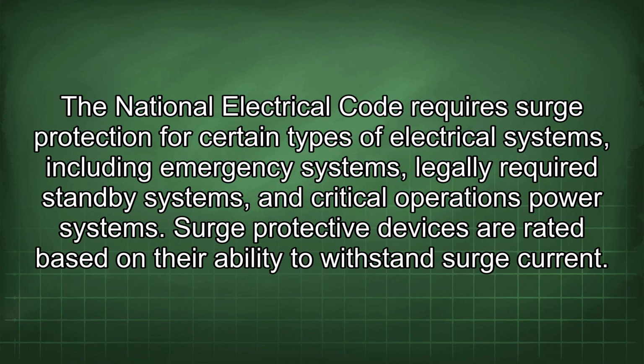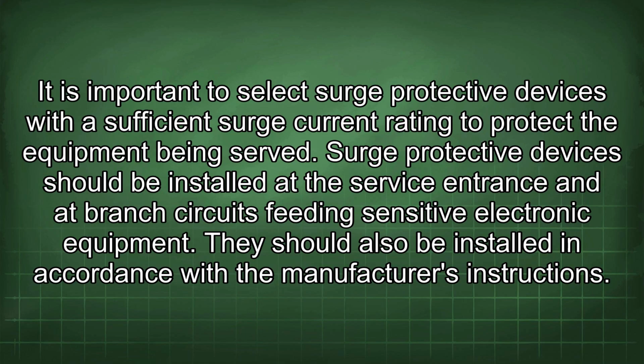The National Electrical Code requires surge protection for certain types of electrical systems, including emergency systems, legally required standby systems, and critical operations power systems. Surge protective devices are rated based on their ability to withstand surge current. It is important to select surge protective devices with a sufficient surge current rating to protect the equipment being served. Surge protective devices should be installed at the service entrance and at branch circuits feeding sensitive electronic equipment. They should also be installed in accordance with the manufacturer's instructions.